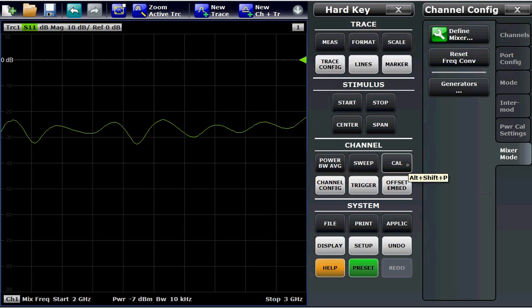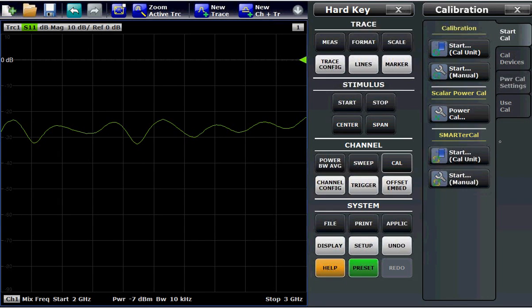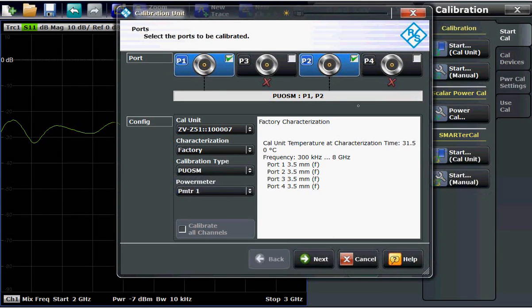I'm clicking on the Cal button to select the Cal menu. Now I can choose either to do the Smarter Cal based on an automatic Cal unit or based on manual calibration. Here today I'm doing it based on an AutoCal unit. This picture shows us that port number 1 and port number 2 are aligned to the Smarter Cal, and the calibration type, which can be chosen in this area here, is set to PUOSM.